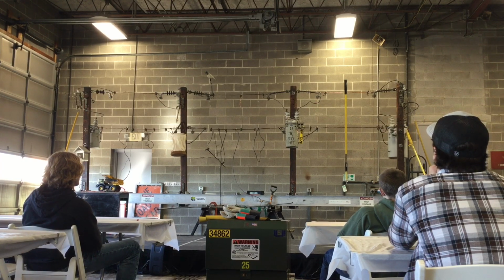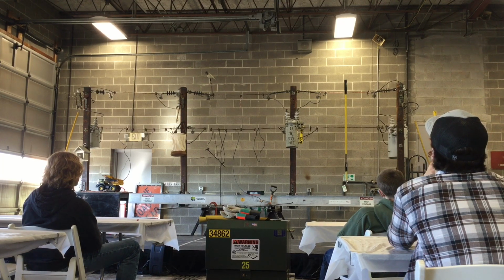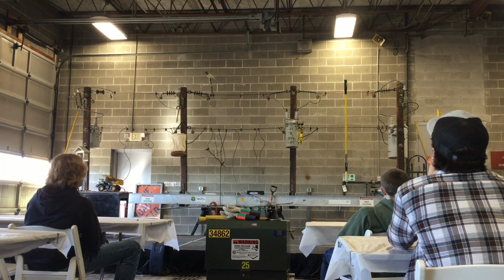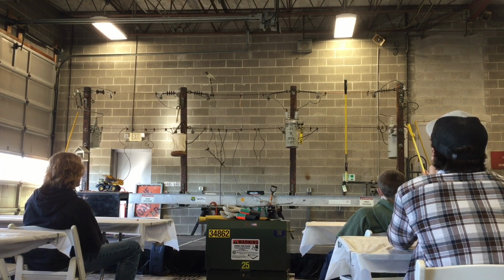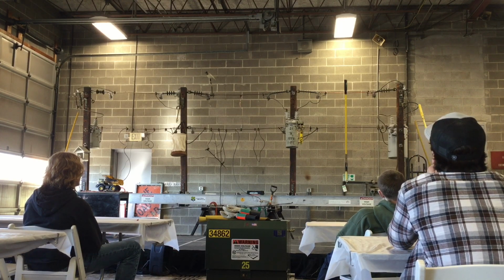But in our case, we're going to step it up, because the transformer doesn't know if the voltage is coming in the primary side and stepping it down. If we put 120 volts on the secondary side, what's it going to do? It's going to step it up because it comes through in reverse, right? So that's what we're doing. We've got 120 volts coming in the secondary, coming out the primary, to this cutout.